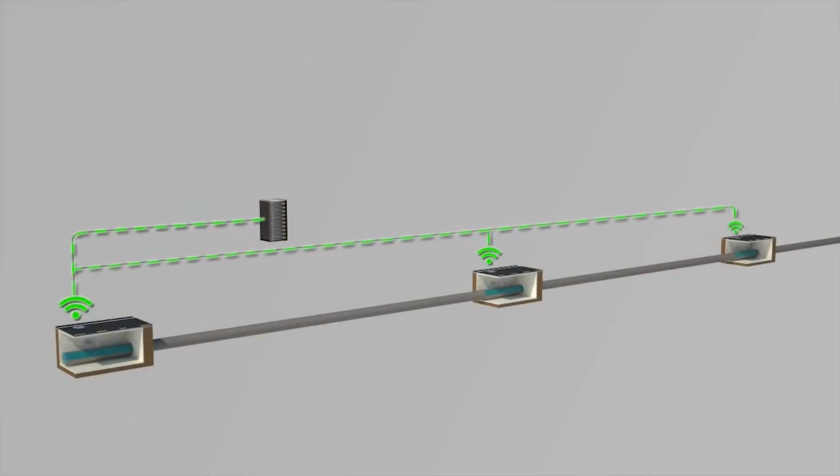So when we imagined monitoring water pipelines for leakage, it was only natural that we thought about a number of other parameters, because when we design the electronics, we can accept virtually any sensor that's 4 to 20 milliamps. So we can monitor pressure, temperature, water quality, and flow, and we can do it in a way that's very different from conventional technologies, because you can have this data anytime you want. It doesn't count on the device waking up at 8 a.m. and sending the data to you. You can wake it up anytime you want, which provides a lot more value to that data.